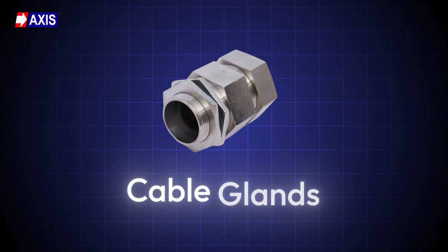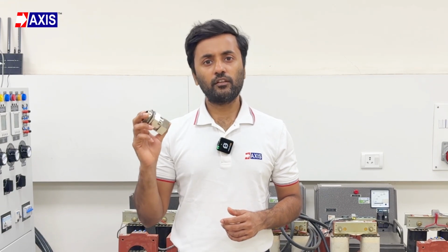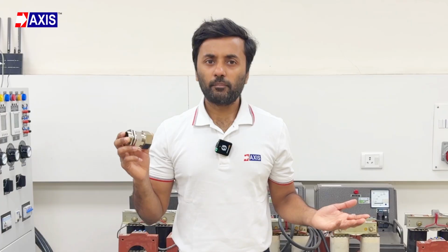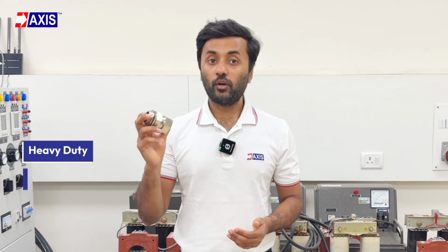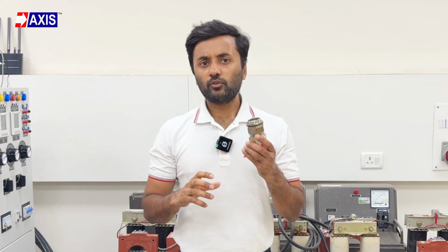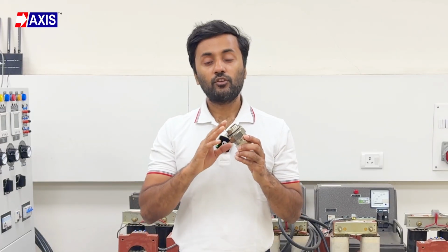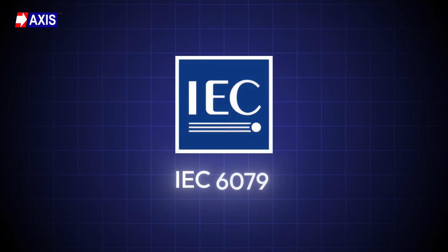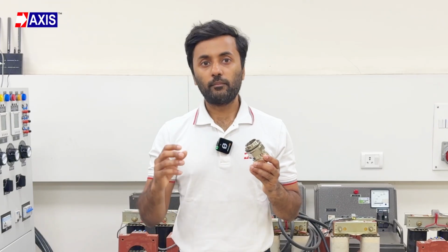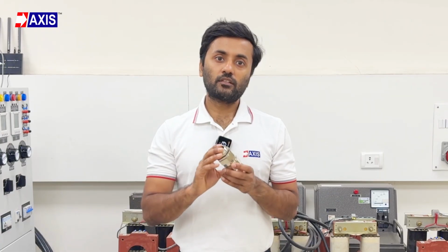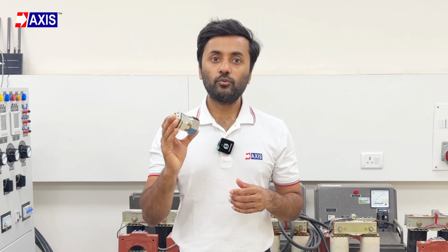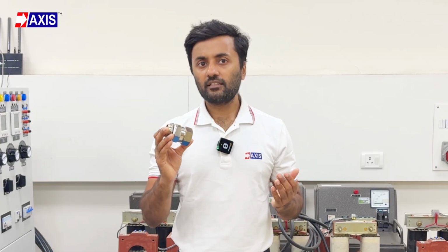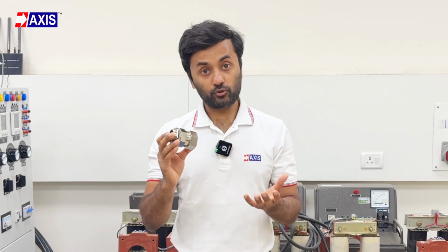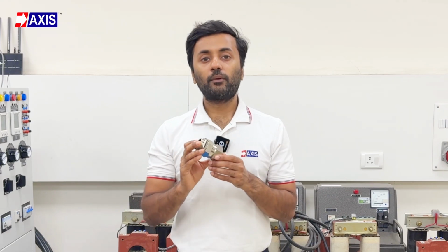Now, cable glands. A cable gland is a component used to seal and secure cables entering an electrical enclosure or combiner box. In solar plants, glands must be heavy-duty, weatherproof, and flame-proof to protect against harsh environmental conditions. To ensure electrical safety, these glands should comply with IEC 60079. This standard specifies requirements for flame-proof glands. It covers the construction and testing of glands designed to be used in explosive atmospheres. This test ensures your gland can withstand internal explosions and pressure without compromising safety.